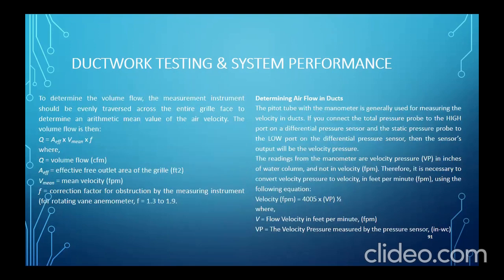So to determine the volume flow, the measurement instrument should be evenly traversed across the entire grill face to determine the arithmetic mean value of the air velocity. So the volume flow is then Q equals A, the effective outlet area of the grill, times V, the mean velocity, times F, the correction factor for obstruction by the measuring instrument. For a rotating vane anemometer, it is 1.3 to 1.9. Okay.